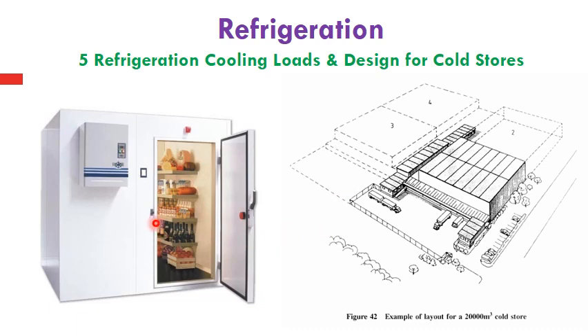This is a sample of a smaller cold store which may be equipped in a hotel or small restaurant. One for fruits, one for veggies, one for meats, one for chicken, one for fish. Each has a capacity of maybe not less than 1 ton, maximum 2 tons of refrigerated space, and can store beverages, dairy products, veggies. Its compressor ranges from 1.5 horsepower up to a maximum of 5 horsepower according to the freezing or chilling temperature to be used.